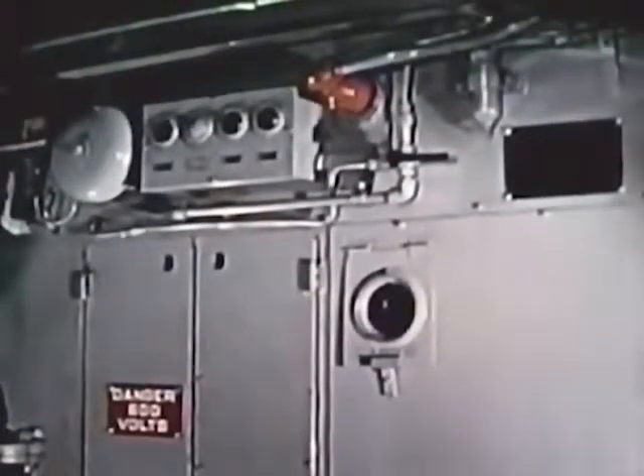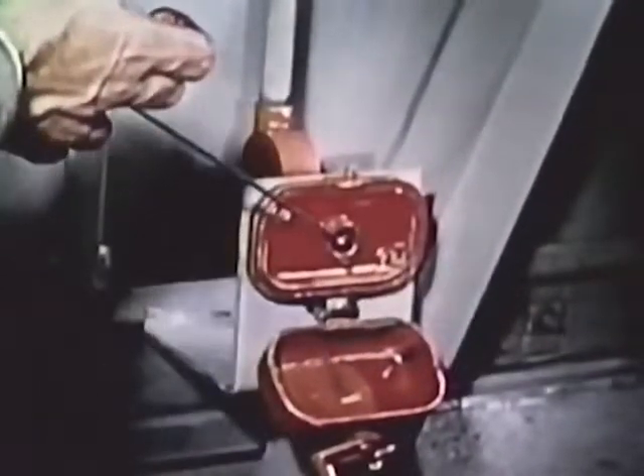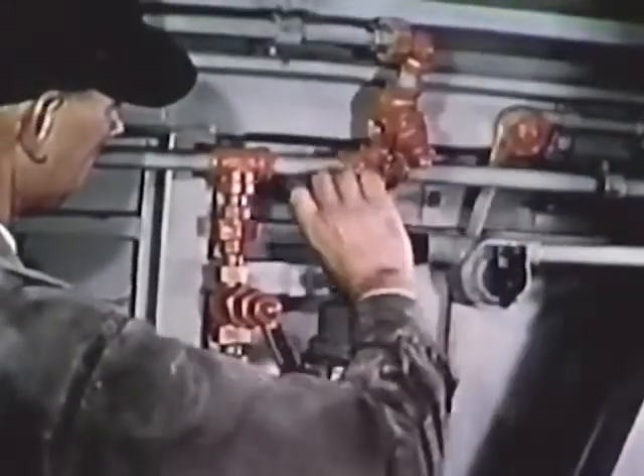Those steps will apply to a lot of fires, but there are some general things to keep in mind in other situations. If the fire occurs in an electrical cabinet which has a built-in CO2 nozzle, all that has to be done is pull the handle in the pull box. Then open the valve located near the cabinet. CO2 will be released inside. Keep the cabinet doors closed.